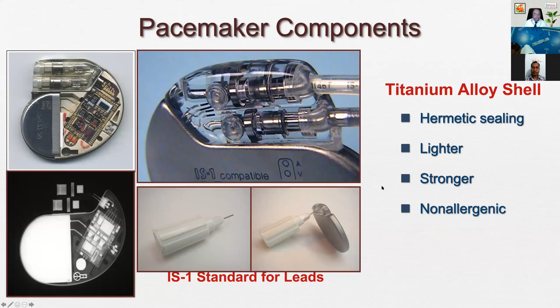Another important component is the reed switch, which gets activated when we place the magnet over the pacemaker. So the pacemaker becomes asynchronous when we place a magnet over it. That is, it stops sensing. That has some utility in certain situations, which we will discuss in the troubleshooting. But right now, this is one of the basic components of pacemakers, called the reed switch, which is present inside and gets activated when we place a magnet over the pacemaker, and it stops sensing.